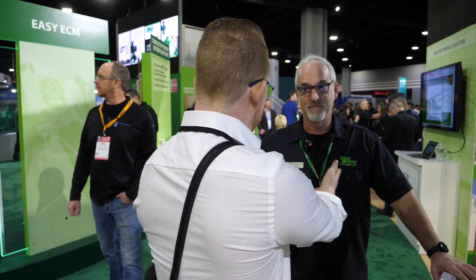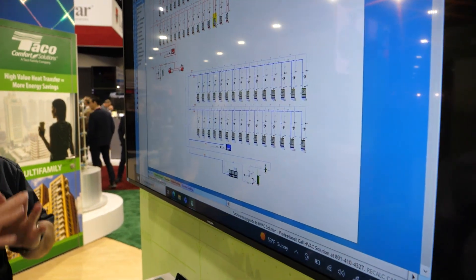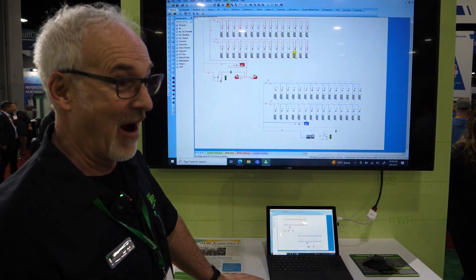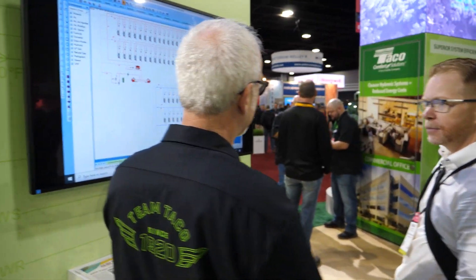At Eden Energy — the day job — we design boiler plants, water to water, air to water. You can build anything in here: air side, domestic side. There really is no limit to what the software can do. The cool component is what's going on behind the scenes — everything's got a load you can associate, and it figures out all those loads together, tells you the pipe size, looks at your head loss, and gives you all those pieces you'd typically have to research. And the thing we should lead with: you don't have to pay for this software. Taco provides it — you can go onto their website, download it, and away you go.